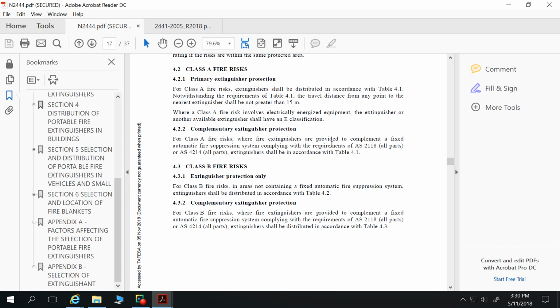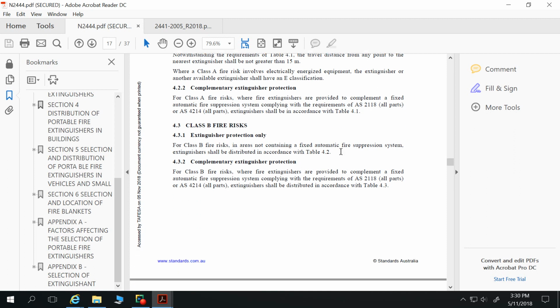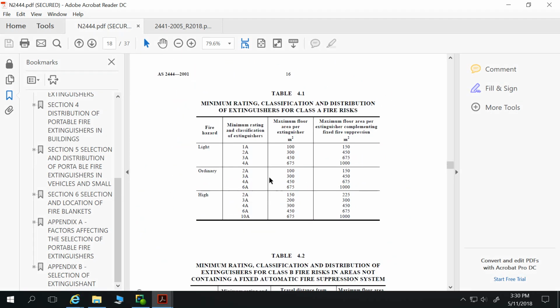And Class A fire risks where fire extinguishers are provided to complement a fixed automatic fire suppression system complying with Australian Standard 2118. Extinguishers shall be in accordance with Table 4.1. So have a quick look at this Table 4.1. So for Class A fire risks, we've got maximum floor area per extinguisher and then maximum floor area if you've got an automatic fire suppression system.